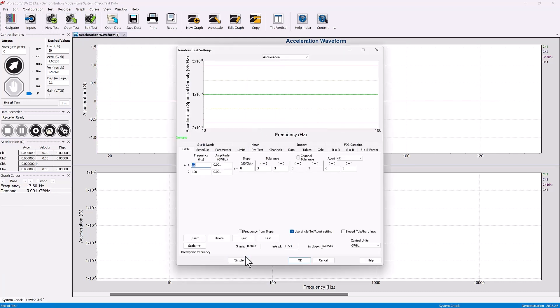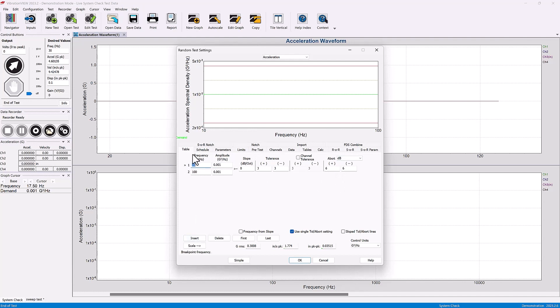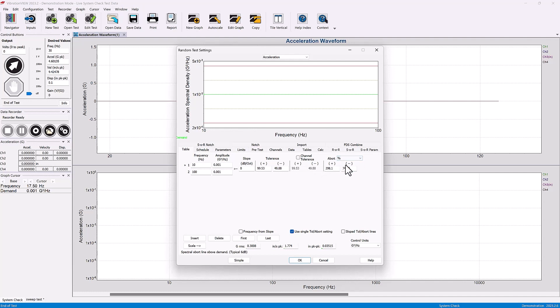In the advanced tab you'll see those abort levels already on the first tab under the table tab where you're setting up your whole profile, your breakpoint table. You are able to change the tolerance levels and the abort levels. Again here you have opportunity to change not just in decibels but a percentage or even a particular G squared per Hertz level.